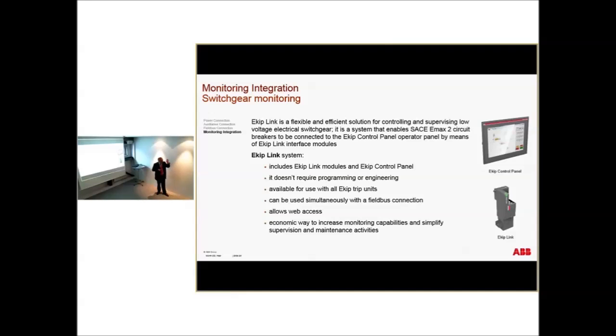So you plug in just a single module, which is called Ekip Link, that is this one, and you have an Ekip Control Panel. Then you have an Ethernet connection, so a very common cable that you can find everywhere. You can basically start from the breaker and go to this one. This one you can operate, you can read all the information, voltage, current, everything that the breaker itself can read, depending on the release you have. And you can decide to operate. You have basically a remote operation of the breaker. And you have also the control and the operation.